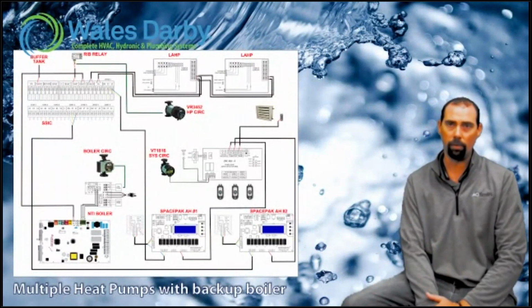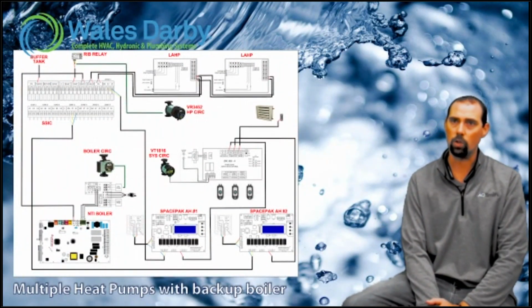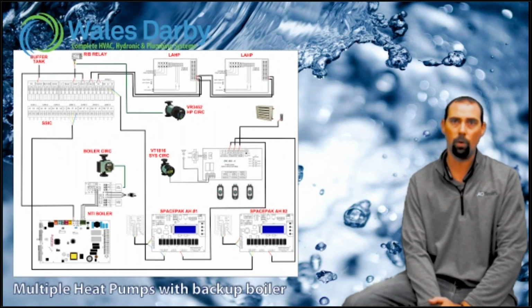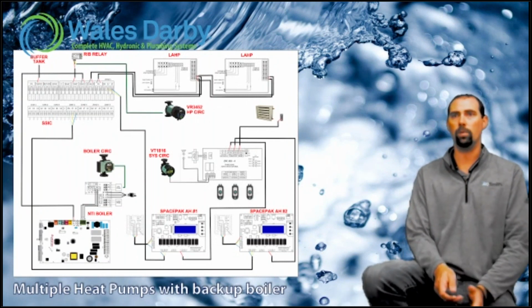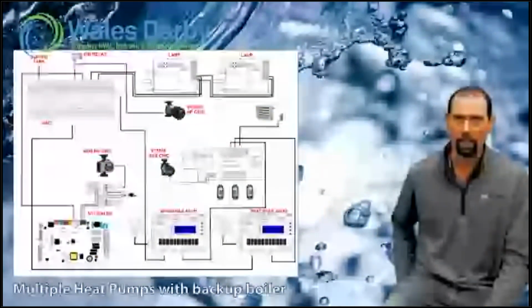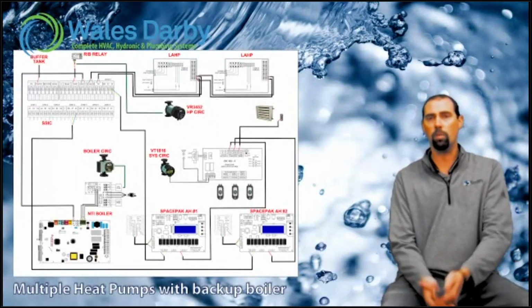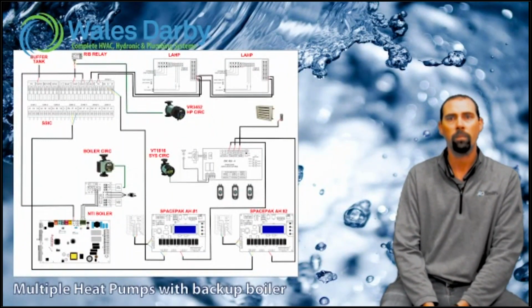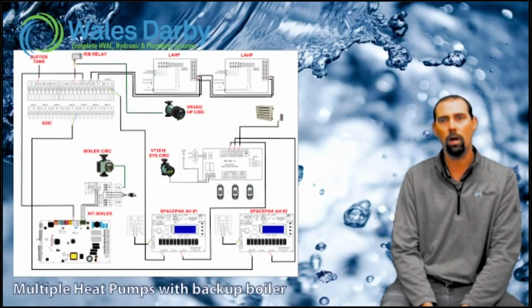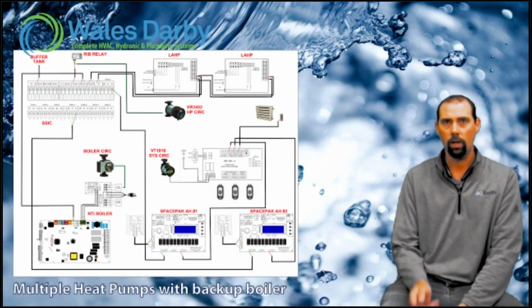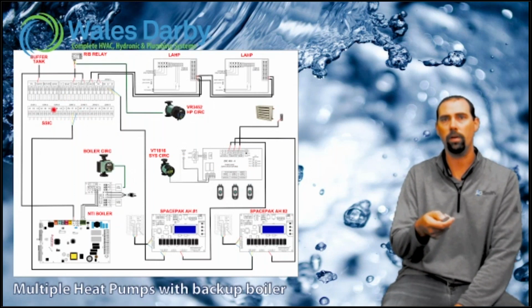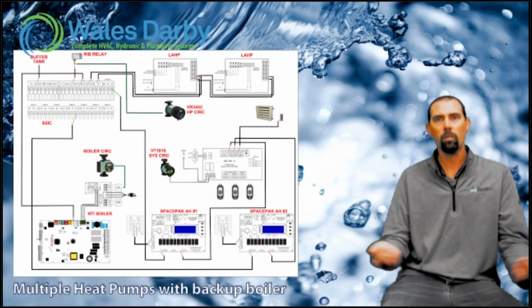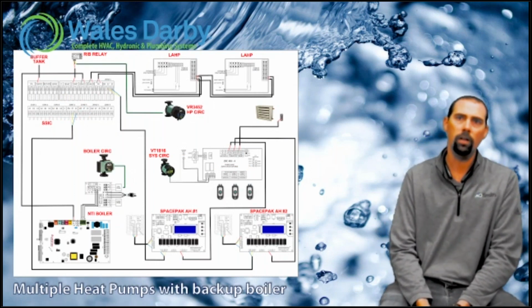This is a layout that we provided, something I put together for the contractor to follow. We can help you guys out with it too if it's your first time doing heat pumps or the wiring, control side of things. This is multiple heat pumps, backup boiler, very simple, a couple 2-wire low voltage wires being run from the boiler to the control. You can see the SSIC up in that top corner. Not very difficult here, everything has a landing spot.